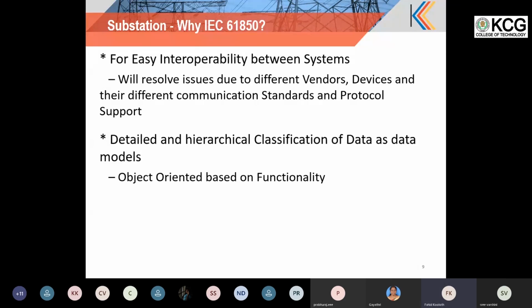Then the data model is completely independent of the protocol. For example, there is Modbus, which is a very primitive protocol, and there can be IEC 101, 103, and a lot of other protocols. All these protocols are ignorant about the data part. For example, a current in Modbus can come from address 2000 in one device, and from address 3500 in another device. So there needs to be a cross reference with all the vendors: where I am getting current, where I am getting voltage, where I am getting breaker status. All these details are needed in all other protocols. So 61850 avoided that with a complete hierarchical classification of data.